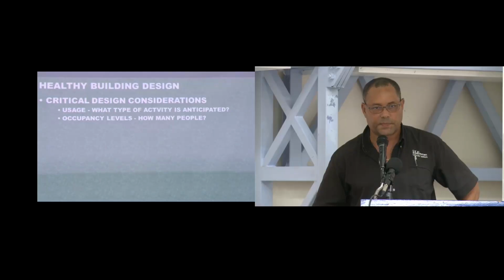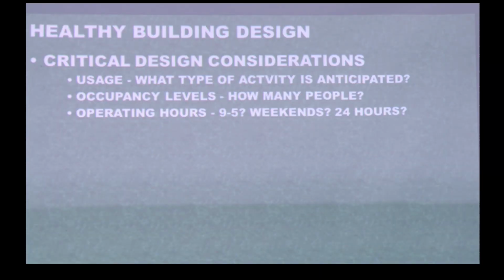Right. The number of persons in a space isn't just the number of bodies, it's the amount of equipment, the type of equipment, how it's going to be used, all that sort of thing. Your operational hours: standard 9 to 5, working on weekends, a 24-hour operation. If it's a 24-hour operation, you don't have your external heat loads anymore because the sun's down. You have to make provision for that. Your system is designed to deal with your peak load, which is the heaviest load you're going to experience during the day. If you're operating at 3 o'clock in the morning, you have to introduce a false load, which is called a reheat, to trick the system into thinking that everybody's still there. So you have to be cognizant of that. Either your system has to be able to ramp down to deal with the reduced load, or you have to increase your load.